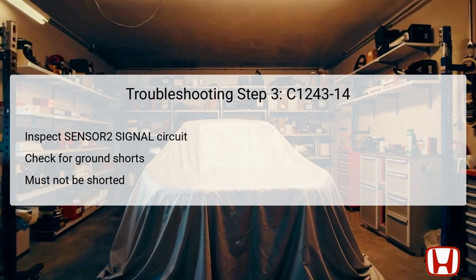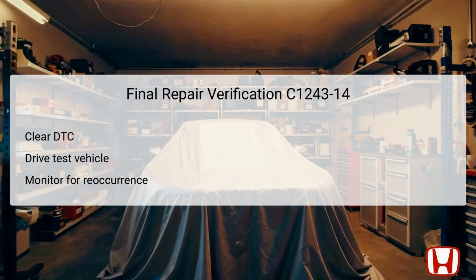Ensuring continuity in the signal circuit while preventing any grounding issues is crucial, as it allows the sensor to transmit accurate data for effective braking functionality. If the circuit is intact, attention may shift back to the sensor itself, which could be at fault if the signal remains problematic.